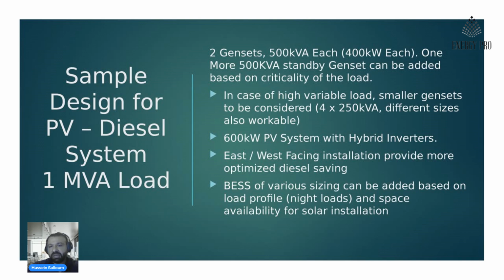Here you can put two generators of 500 or four generators of 250. Different sizes are also available - two of 250, one of 200, one of 300. It's not a big deal. The issue is that the variability of the load defines the multiplicity of the generators you can put. The more variability, the more controllable it is for you than putting one generator for one size.